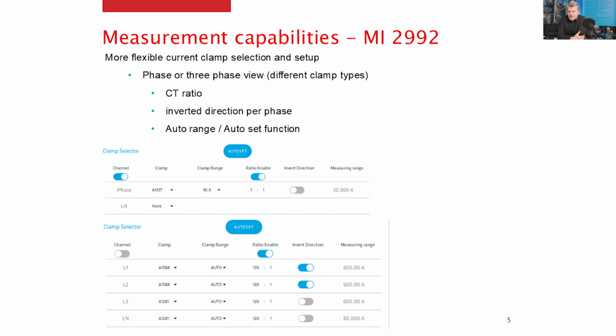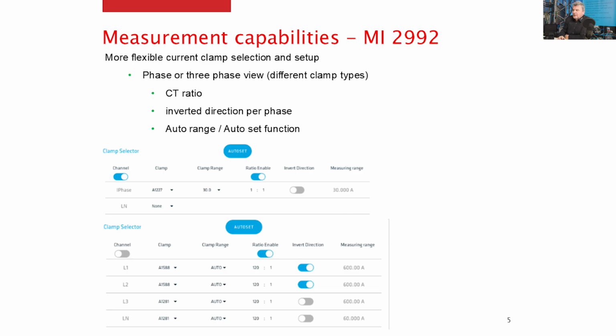If we focus on the functionality of current clamps, we implemented a new functionality which was requested by the market. You can select different current clamps for a specific input. In this case, we have a three-phase view, where for each phase input and neutral, you can use specific current clamps. For example, you use a flex clamp for input 1, a DC clamp for input 2, and a third type for input 3. We also have a total view when all phase clamps are joined together, and setup is done with a simple click on the clamp range, ratio, and direction.